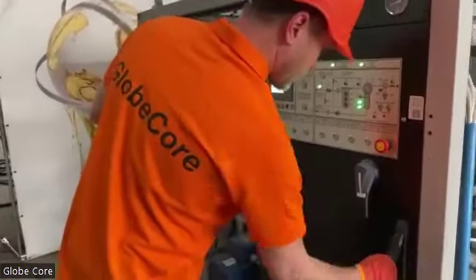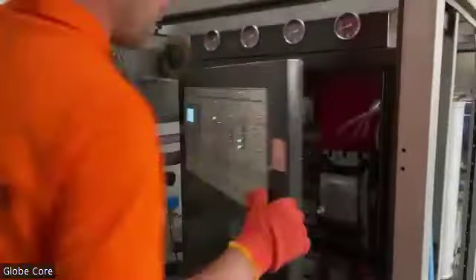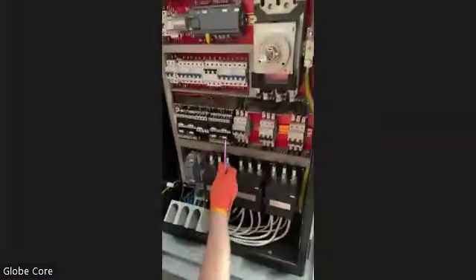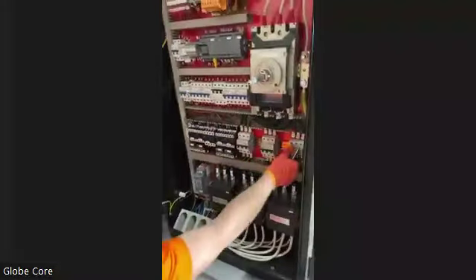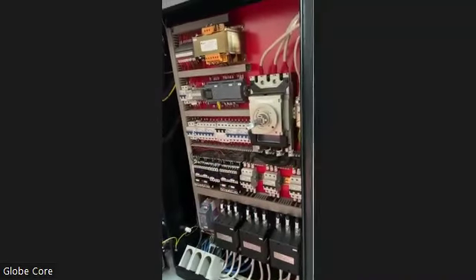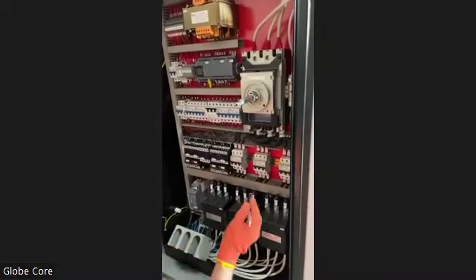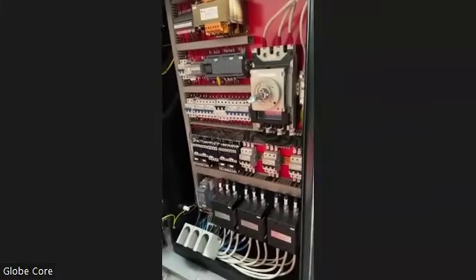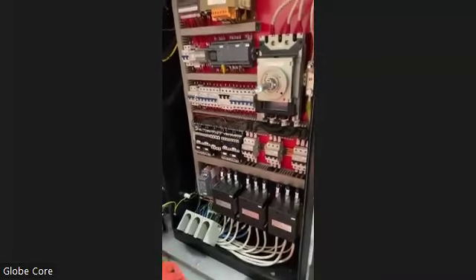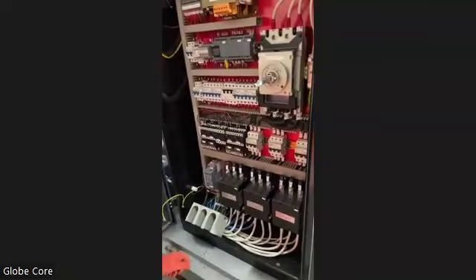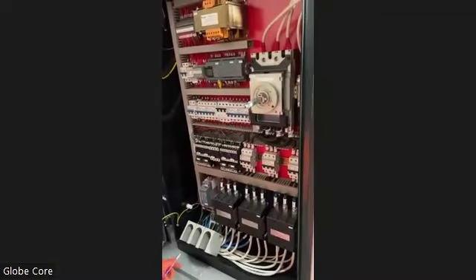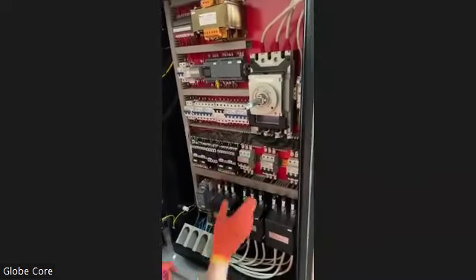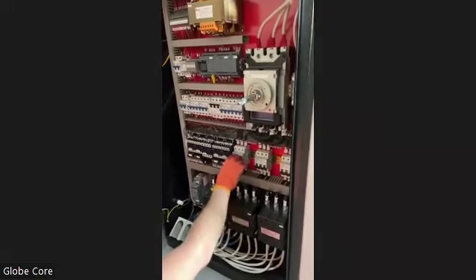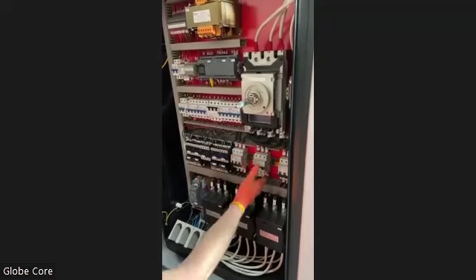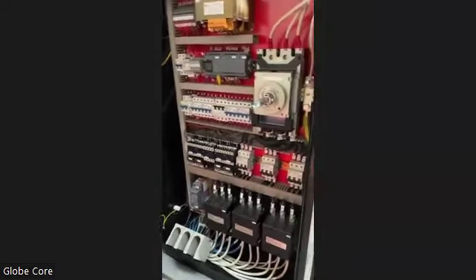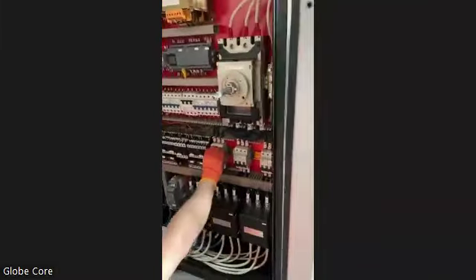Let me show you. So we have the switchers for each section of the heater. They are here. So you can activate all 3 sections of the heater to see the algorithm of heating operation. But if you work with a 35 square millimeters cable, keep in mind that only one section should physically work. So you can choose any of them. You can choose the second one or third one, but if you work with such a small cable, keep in mind that you can only run one section of the heating.